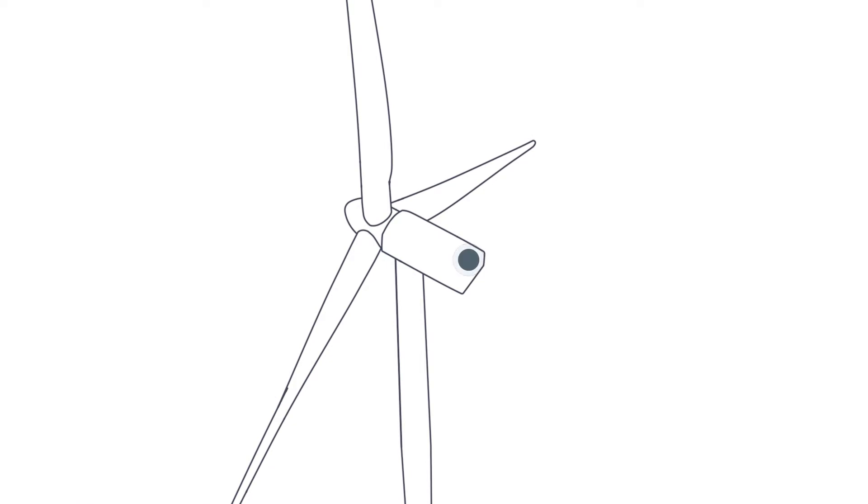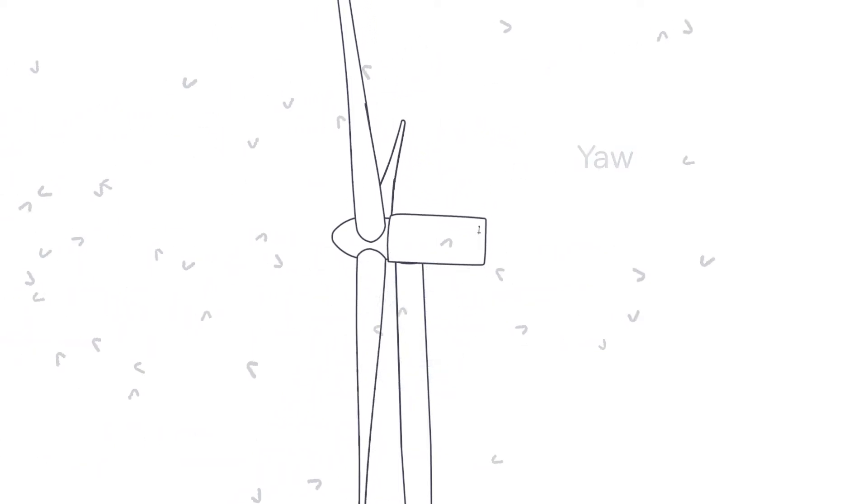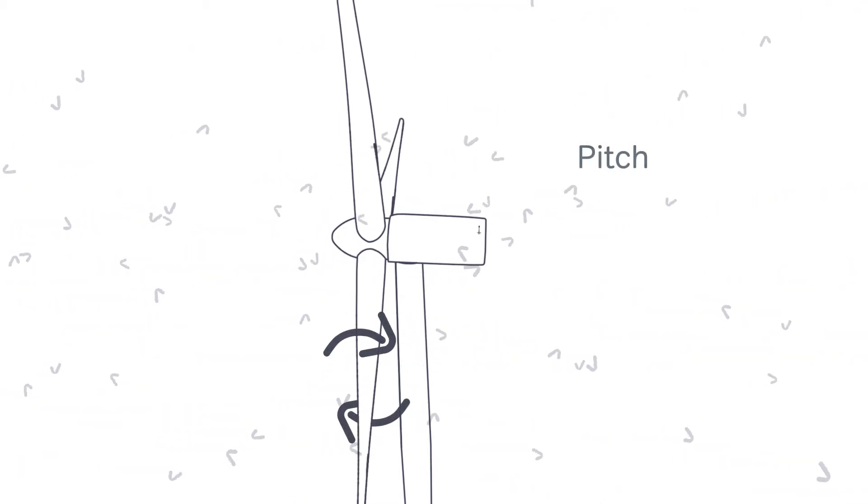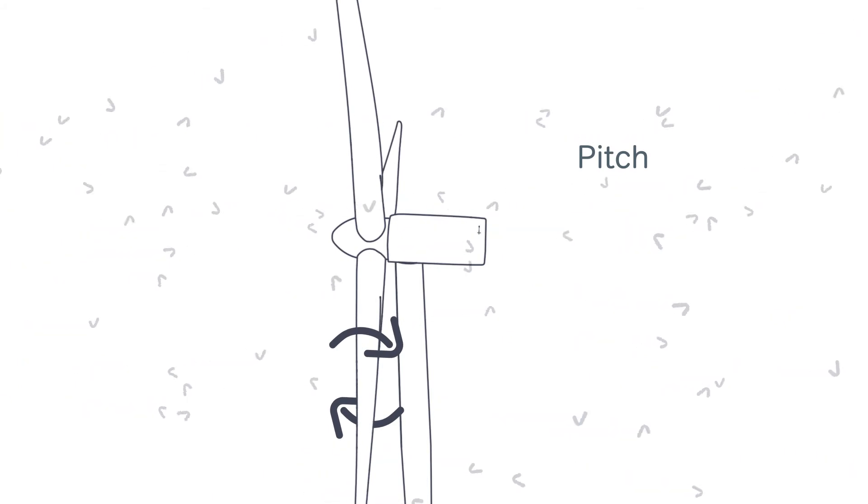The wind vane, for instance, measures the direction of the wind. This data is used to control the turbine's yaw system, aligning the rotor to the wind to optimize output and minimize strain. The main controller also adjusts the pitch of the blades to match the force of the wind.